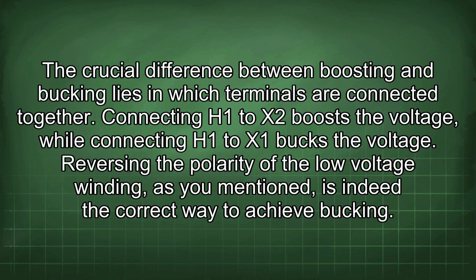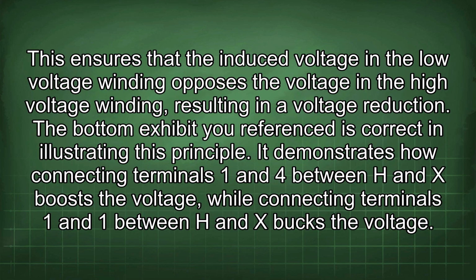Reversing the polarity of the low voltage winding, as you mentioned, is indeed the correct way to achieve bucking. This ensures that the induced voltage in the low voltage winding opposes the voltage in the high voltage winding, resulting in a voltage reduction. The bottom exhibit you referenced is correct in illustrating this principle. It demonstrates how connecting terminals 1 and 4 between H and X boosts the voltage, while connecting terminals 1 and 1 between H and X bucks the voltage.